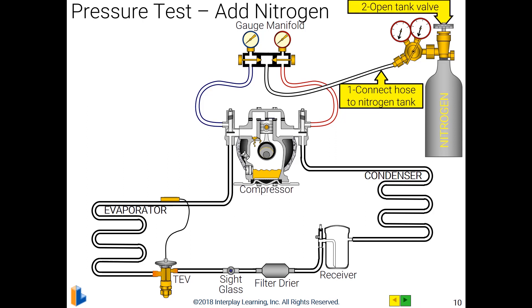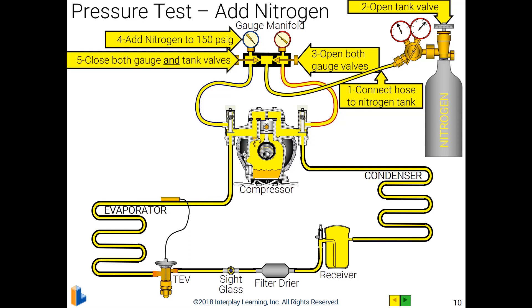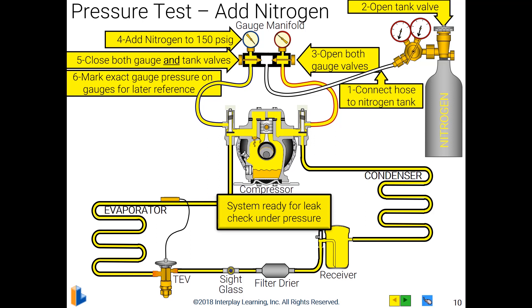For an R22 system, we set our regulator to just over 150 PSIG. We open the tank, open the valves on the gauges, and fill the system with nitrogen, dialing in at exactly 150 PSIG and stopping. We close both gauges on the red and blue and turn off the pressure on the tank. We don't want any leaks in our gauge manifold throwing off our pressures. We don't really need to mark the exact gauge pressure since we use the same pressure every time. The system is ready to go.